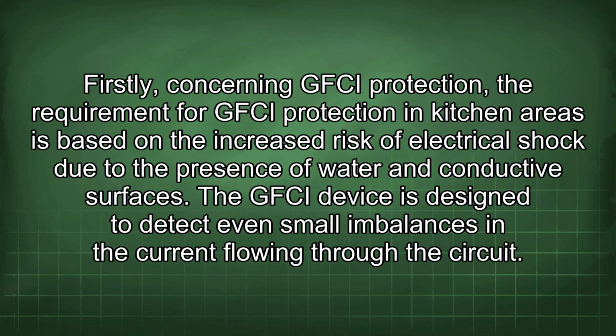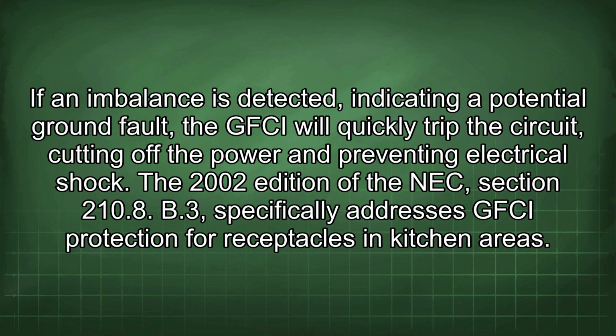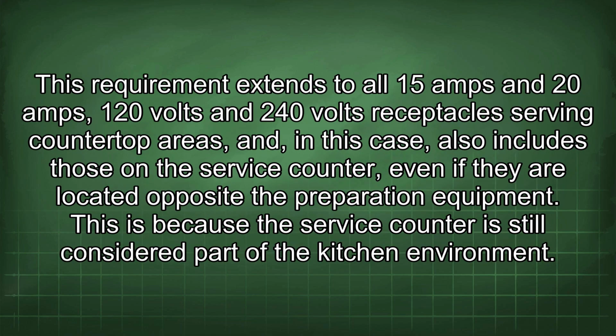Firstly, concerning GFCI protection, the requirement for GFCI protection in kitchen areas is based on the increased risk of electrical shock due to the presence of water and conductive surfaces. The GFCI device is designed to detect even small imbalances in the current flowing through the circuit. If an imbalance is detected, indicating a potential ground fault, the GFCI will quickly trip the circuit, cutting off the power and preventing electrical shock. The 2002 edition of NEC Section 210.8(B)(3) specifically addresses GFCI protection for receptacles in kitchen areas. This requirement extends to all 15 amp and 20 amp, 120 volt and 240 volt receptacles serving countertop areas, and, in this case, also includes those on the service counter, even if they are located opposite the preparation equipment. This is because the service counter is still considered part of the kitchen environment.